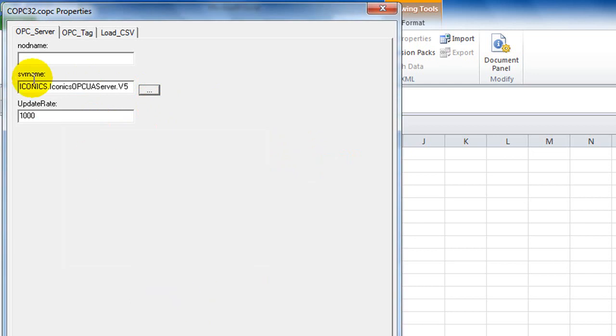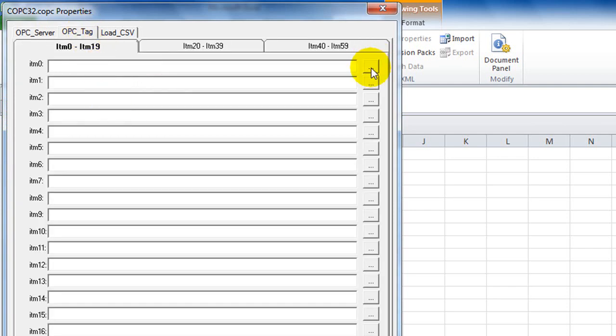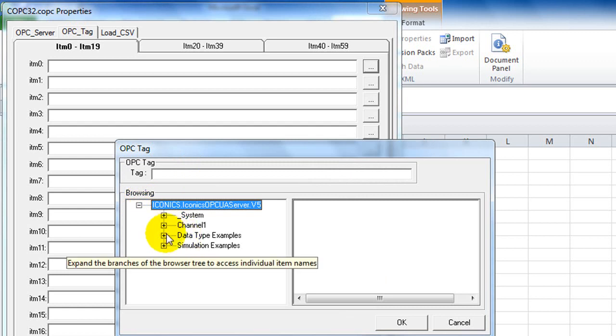Select the OPC server you want to connect to and click OK. Specify the update rate in milliseconds — in this case, the update rate is 1000 milliseconds, which is one second. For Step 2, choose the OPC tag you would like to connect to. The OPC server you selected will display its available tags.